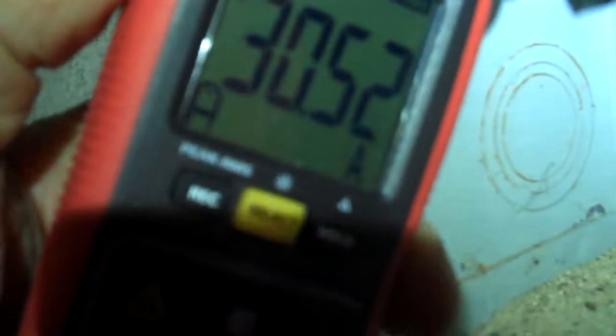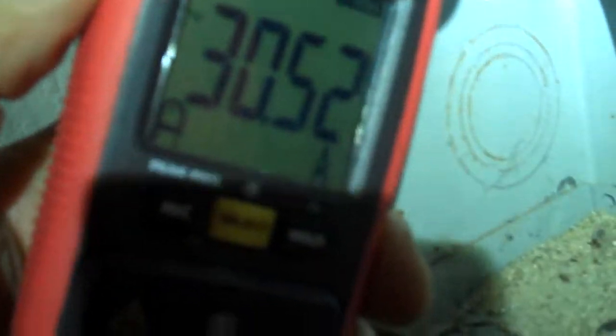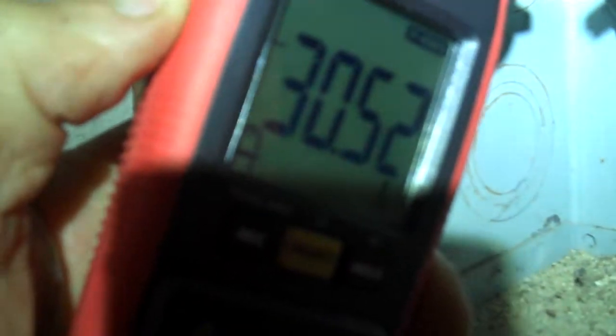Okay, this measurement came out at 30.52. So you can see this is a little bit over the 30 amps. And initially it said 0.2, so there are a couple of tenths here. It may not be accurate to the tenth, but the other one was 30.29, this is 30.52. I could repeat this measurement a couple times and might make it more accurate, but you get the idea. It's basically drawing 30 amps, and it's a little bit over. So that's interesting, and it seems like that might be behaving a little bit normal. And the current might have gone up a little bit due to the age of the pump, but I wouldn't say there's anything wrong with the pump. That's probably just something I can put into my budget for my generator.